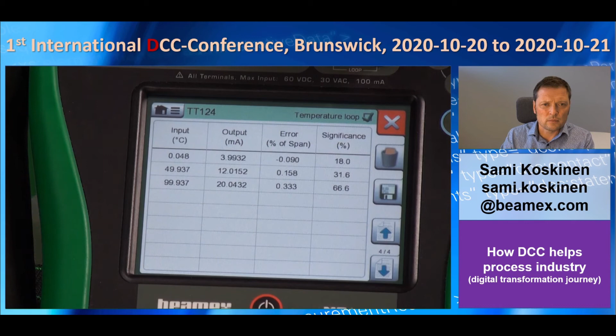If we decided that for some reason we wanted to do a trim, we could do that. We just press this upper left-hand button and start communicator. We could calibrate this as a HART transmitter. If it were a Foundation Field Bus transmitter or even a Profibus transmitter, we could do all three types.